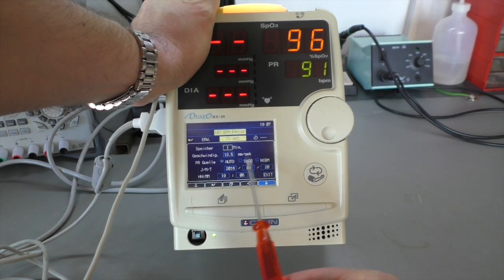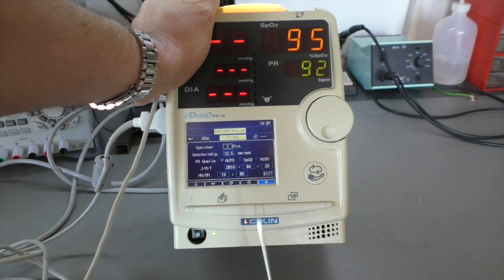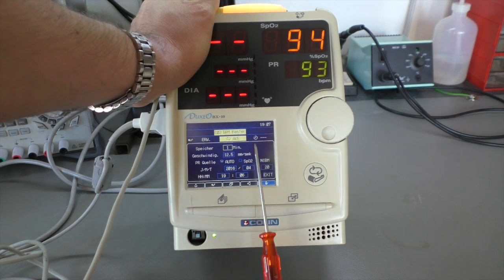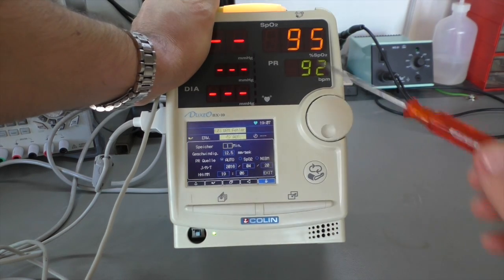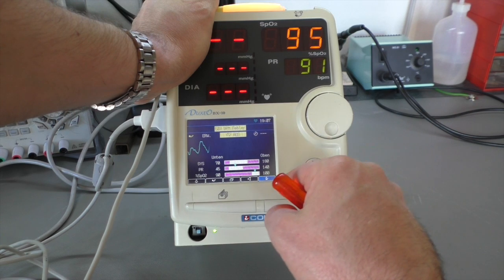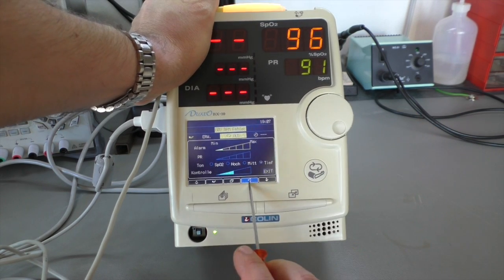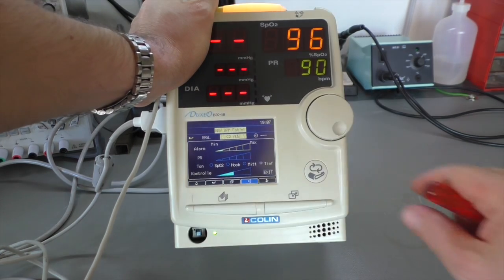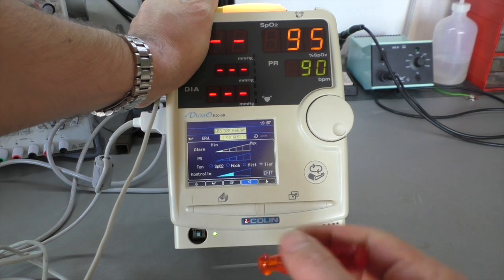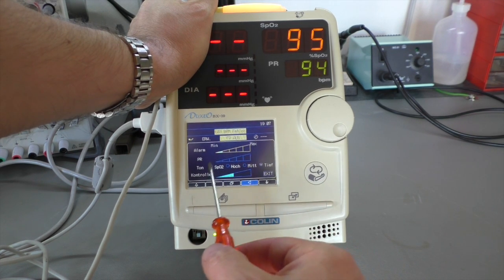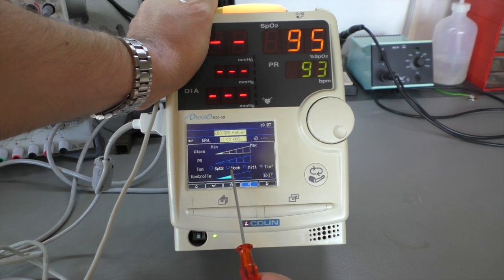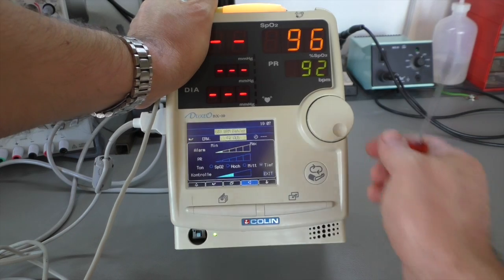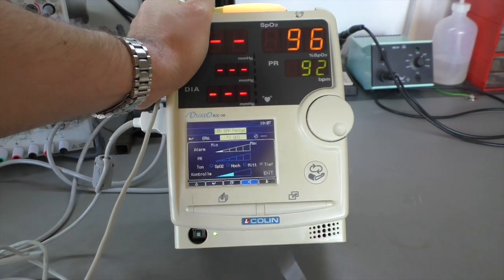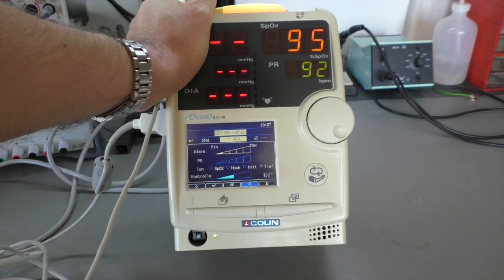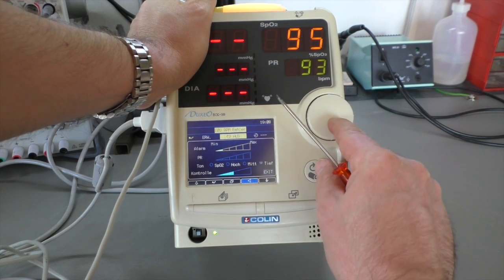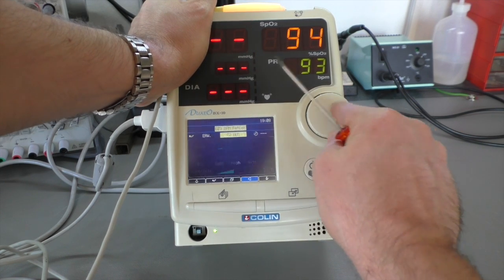There is also the speed of, I don't know, you can attach a printer, maybe it's for that. Then you have the date and the time, you can set the time and date, which is important if you have logged data. In this menu here with the speaker symbol, you can set the alarm volume and the control tone. You can set how the sound sounds, so you can have a high, a medium and a low frequency alarm. So for example, if you have more than one unit in one room, you can say one patient has a high alarm sound or something like that. Okay, exit.